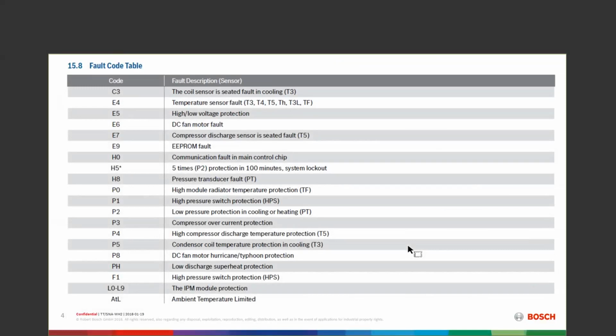So when we're looking at the fault codes, a lot of the fault codes are the same from the 1.0 to the 2.0. Somebody asked me the other day, well, Fred, what's the number 1 fault code that you have? It's down here at ATL. My machine, this 2.0 machine, is an air conditioner down to 15 degrees. It's a heat pump all the way up to 86 degrees. It's a heat pump down to -4. It's an air conditioner all the way up to right around 122, 125 degrees. So got some really large ranges to it. But if we get outside of that range for any particular thing, we're going to see an ATL fault code.